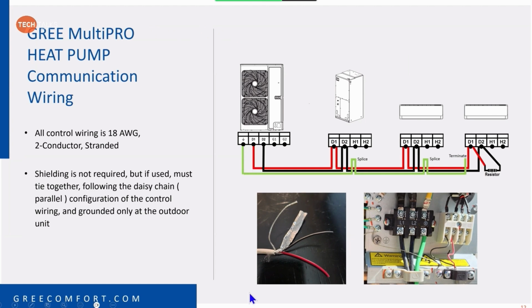And then as you have your cables, such as this right here, going into the indoor unit, like this air handler, for example, it would have two of these cables, one coming from the outdoor unit, one going to your next indoor unit. What you want to do is hook up your D1 and D2s, and then take your grounds and splice them together. Realistically, you don't even have to use a wire nut. That ground wire is so fine. All you have to do is twist it together, and then what I'll tell guys to do is lay that back on that casing and just wrap it with electrical tape.